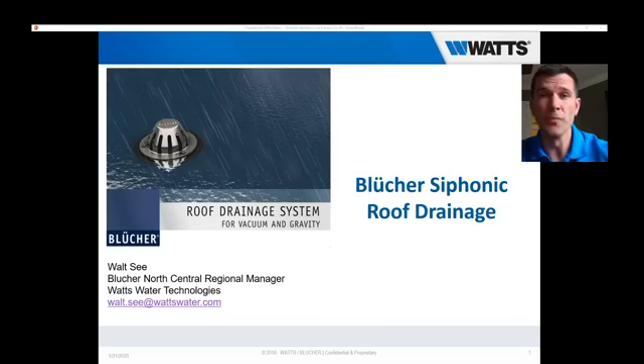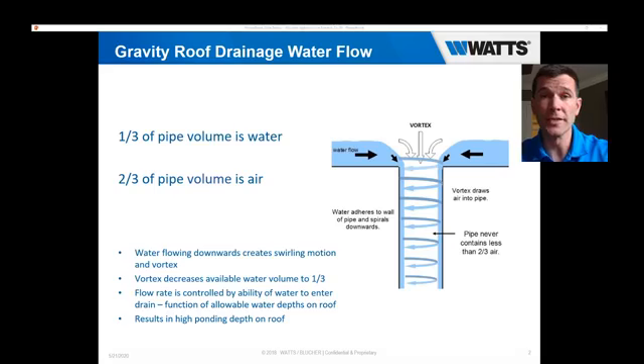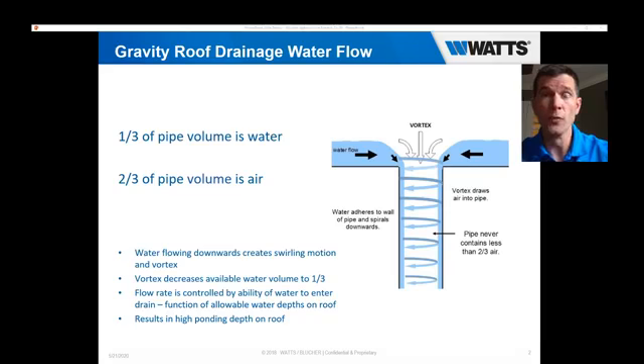To understand siphonic roof drainage, we have to understand the principles of standard gravity flow and gravity roof drainage. With a gravity drain, water flowing downward through the slope on the roof goes to the drain, and as it goes down the vertical pipe, it creates a swirling or vortex motion. The water adheres to the sidewalls of the pipe and clings to the walls on the vertical. So you're only having a third of the pipe volume that's full of water, where two-thirds of the volume is full of air — a pretty inefficient flow option.